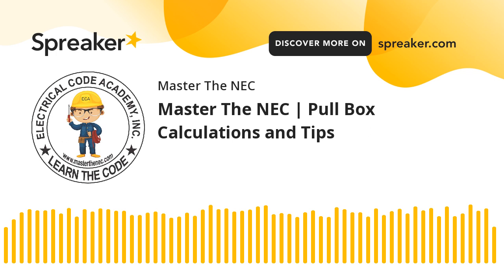And of course, you could have an uninsulated conductor inside of a cable assembly. MC, it's notorious for that. But it doesn't matter because here it's saying cables are included. As long as the cable contains conductors that are 4 gauge and larger, then you're going to follow these rules. All right. So first thing that we look at in here is, well, what are you going to use in order to do this calculation? Do you use inches? Do you use trade size? What do you do? Well, when it comes to raceways, the diameter of the raceway, we're going to use what's called a metric designator. We're going to call it trade size.